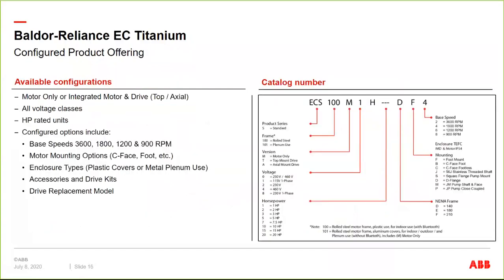This is what I actually talked about from a configured offering. Our standard stock unit is 1800 RPM. However, we have pre-engineered the windings for 3600, 1200, and 900 RPM. We can do different face mountings. We do have new enclosure types coming out. So the standard product with Bluetooth has plastic covers, and we have an option to use metal covers if you have a plenum use application. And we have different accessories and kits that I'll be talking about. And it's a fully serviceable product, meaning that the drive can be replaced separately from the motor or vice versa. So if something happens to the motor or something happens to the drive, you don't have to replace everything. You can just service that individual component.